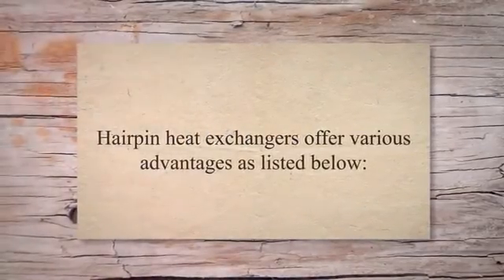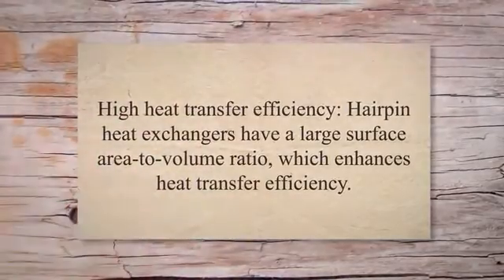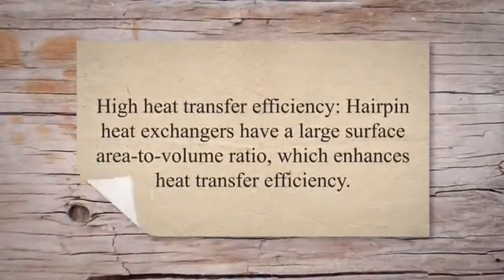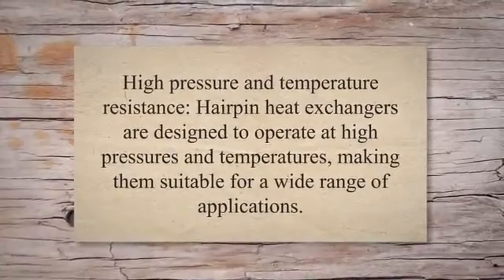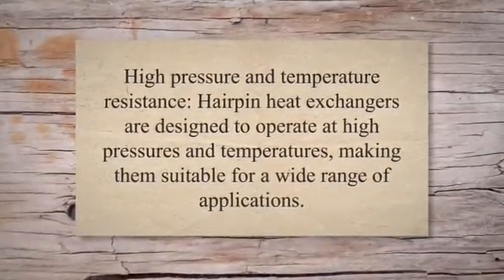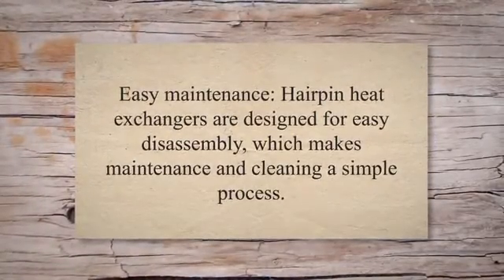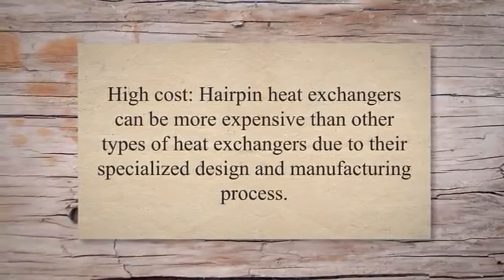Hairpin heat exchangers offer several advantages: high heat transfer efficiency due to a large surface area-to-volume ratio; a space-saving compact design; high pressure and temperature resistance making them suitable for a wide range of applications; long-radius U-bends for effective thermal expansion; easy maintenance through simple disassembly; and no internal bolting. However, one notable disadvantage is high cost, as hairpin heat exchangers are more expensive than other types due to their specialized design and manufacturing process.